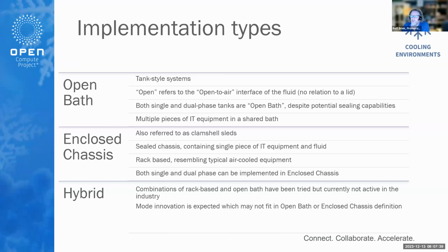As soon as you have a shared volume of fluid between multiple pieces of IT equipment, that's what you're talking about with open bath systems. Whereas enclosed chassis, also known as clamshell designs, are sealed and liquid-proof, containing typically a single piece of IT equipment, usually rack based, similar to air-cooled racks as we know them. Hybrid systems can be combinations - there's a broader definition where we can also look at combination with cold plates, but let's not get into too many details. Here's a couple of viewpoints.